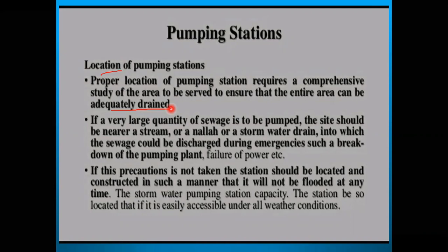What is the second point? If a very large quantity of sewage is to be pumped, the site should be near to the stream or the nala, or the storm water drain into which the sewage could be discharged during an emergency, such as breakdown of the pumping plant or failure of power. So when unexpected events happen, like breakdown of the pump, failure of the pump, or loss of power, keeping emergencies in mind, the sewage could be discharged during the emergencies.